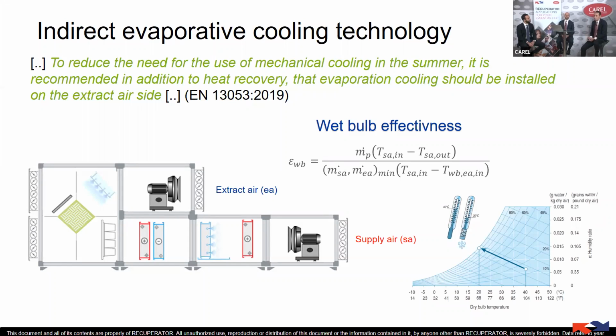This technology is called indirect evaporative cooling. It works by using a water spray humidifier, placed on the extract side of an air handling unit, to increase the humidity to saturation while, at the same time, using the adiabatic cooling effect of the adiabatic humidifier to reduce the temperature. So this technology can get more efficiency from the unit itself, and it is promoted by the norm and regulation.